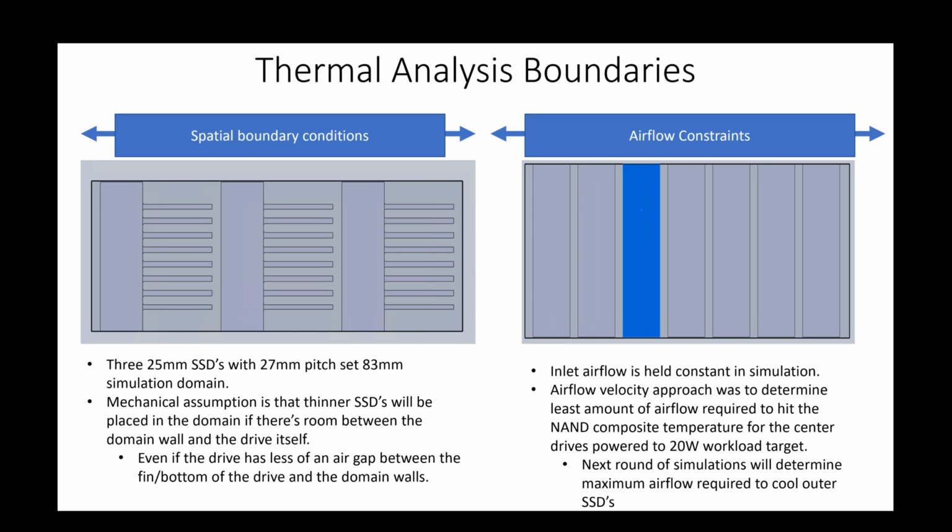Right. So the way that we scale is I've taken the worst temperature and I've scaled to the worst component, and then that will give you either the maximum power that you can get or the minimum power that you'll get in that domain. So let's say in that domain for 3 versus 5, if 3, your minimum power that you will achieve is 30 watts when you scale to the composite of the least margin composite, then you get 30 watts. But let's say the maximum power you can get out of one ruler in that domain is 34 watts.